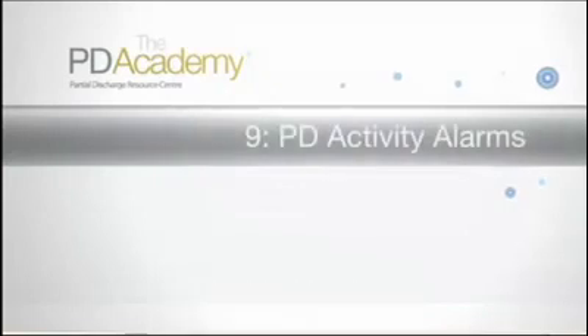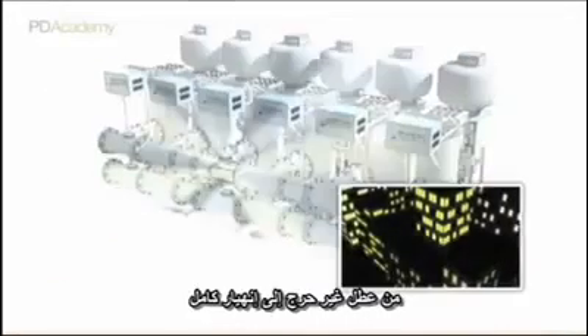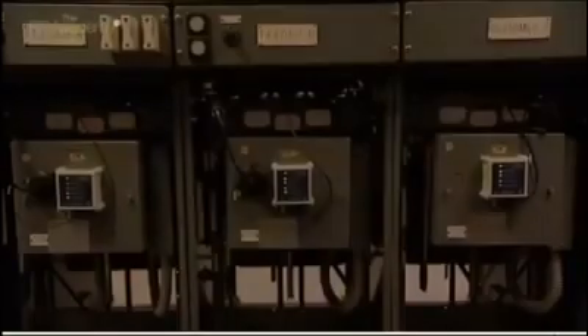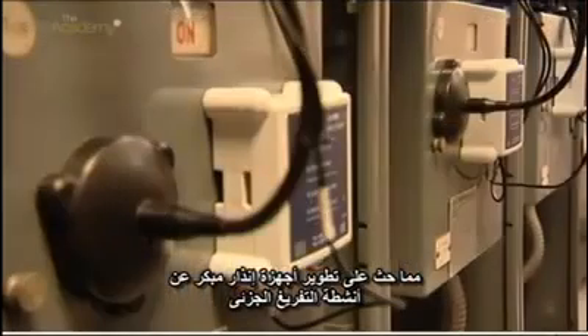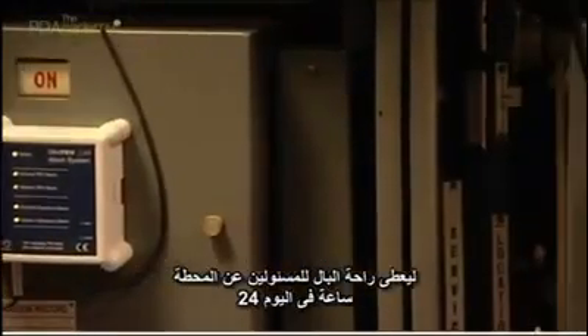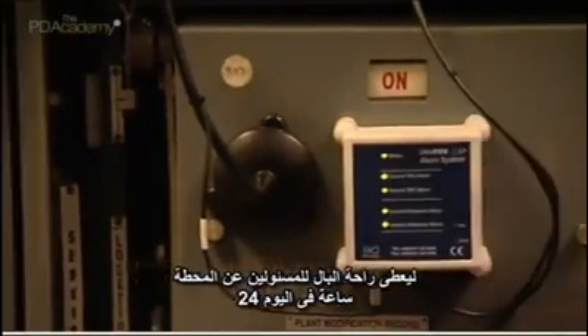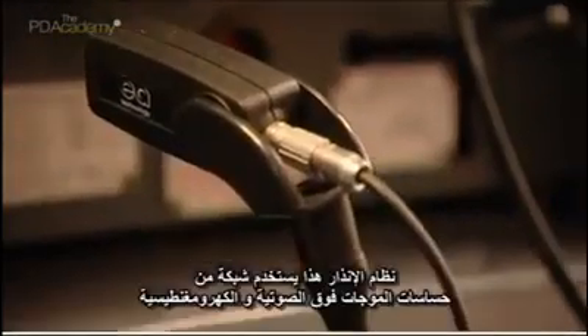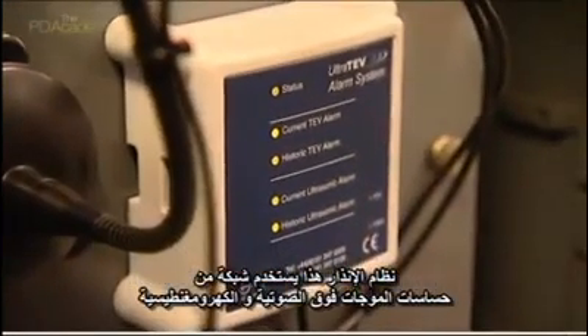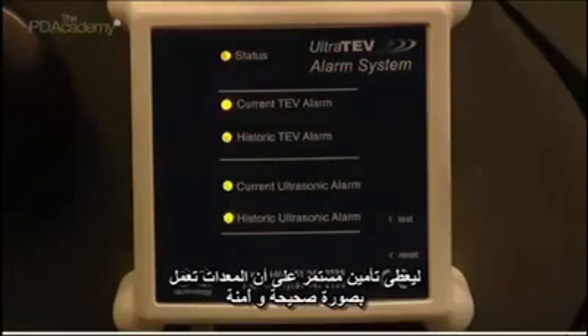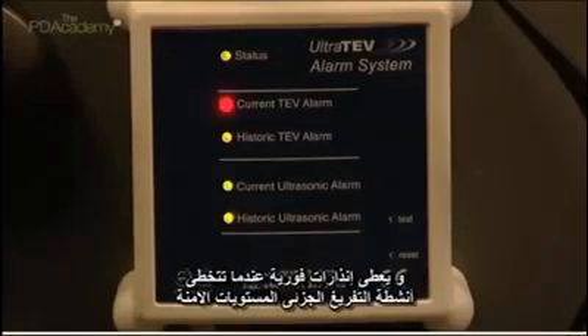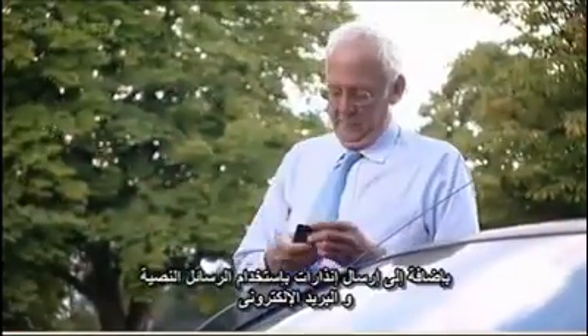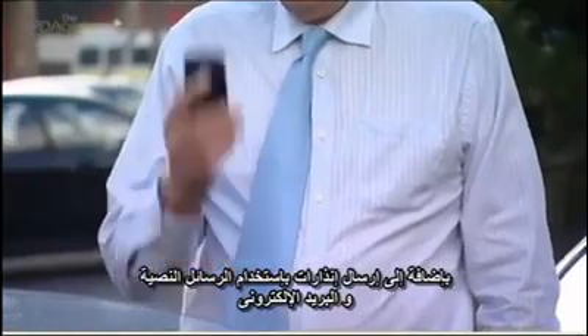PD activity alarms. In some situations, PD activity can escalate rapidly from a non-critical fault into a sudden failure. This has led to the development of PD alarms and early warning systems to give operators of mission-critical assets complete peace of mind 24 hours a day. This alarm system uses a network of ultrasonic and transient earth voltage sensors to provide continuous assurance when substation assets are working correctly and instant alerts if PD activity turns critical using lights and audible alarms. Plus the option of automatically transmitting fault messages via email or text message.